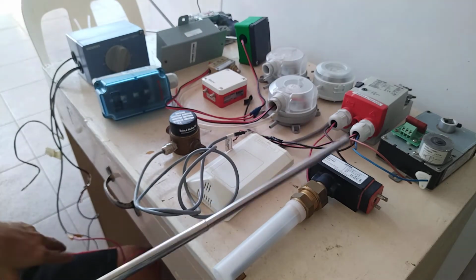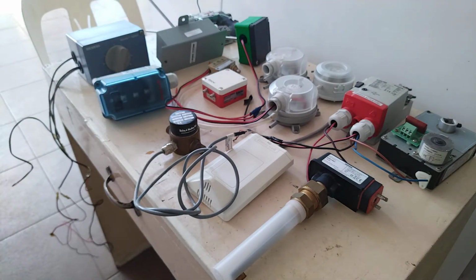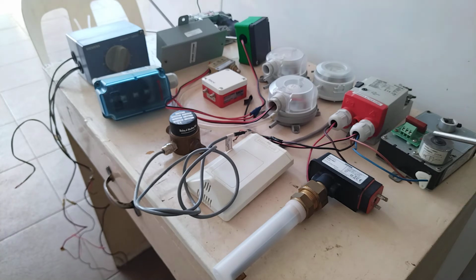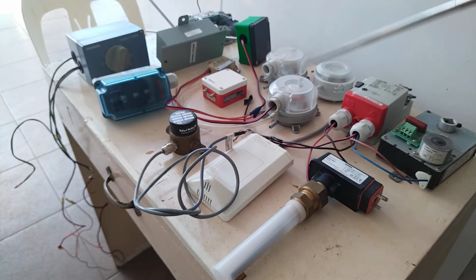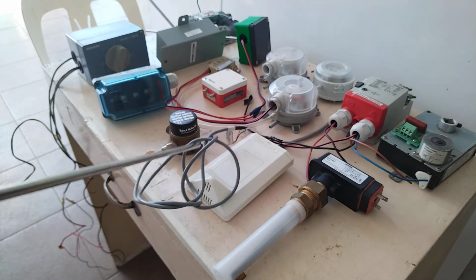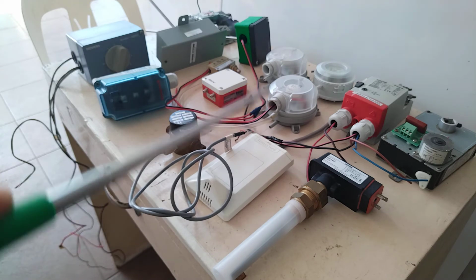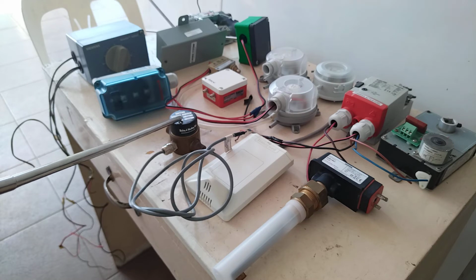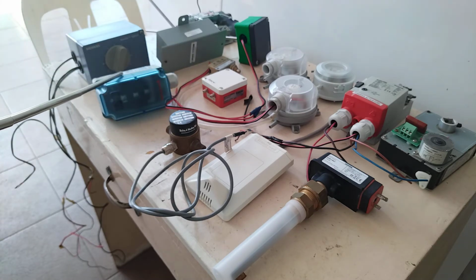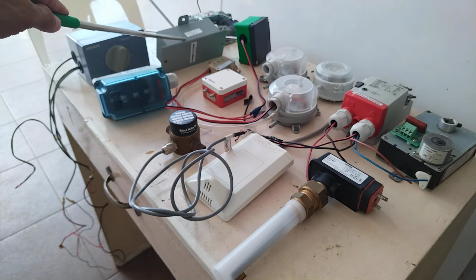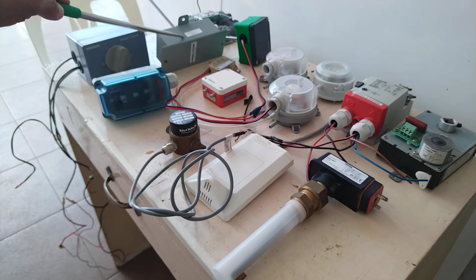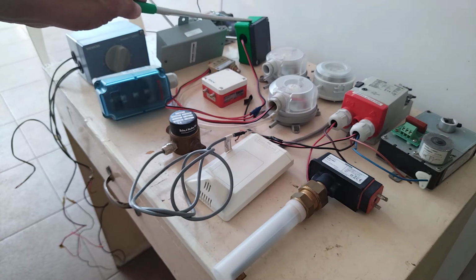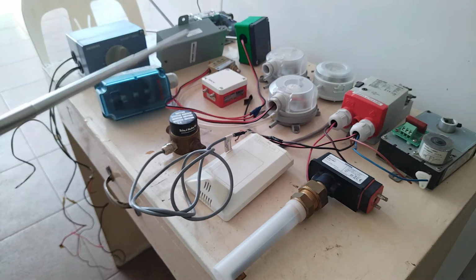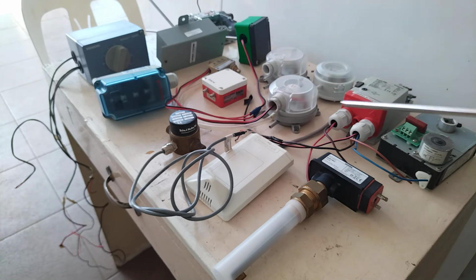So again, to wrap it up, what I have here is a water flow switch, valve actuator, damper actuator, modulating type, then damper actuator, open and close type, differential pressure switch, ambient condition monitoring for outside air relative humidity, water differential pressure sensor, air differential pressure sensor, water flow switch, valve actuator, absolute pressure sensor, duct absolute pressure sensor, water flow switch, usually used for pump monitoring if the pump is delivering water, then this duct air temperature sensor. So basically, these are the most common BMS field devices that you will encounter in the field.